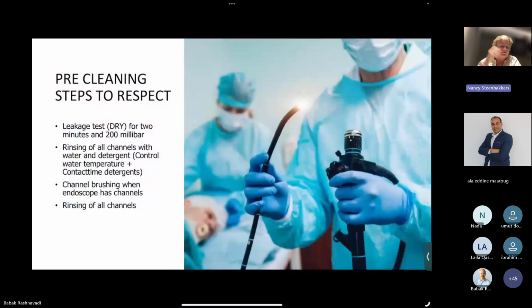Now, the pre-cleaning steps to respect are actually these, and don't forget, these are really the only 4 steps you have to do. So leak testing in a dry condition for 2 minutes at 200 millibar. You have to do it dry. Why? Because in the last 30 seconds of those 2 minutes, you will find out the tiny leakages, and it's the tiny leakages which are giving the headaches in endoscopy departments.